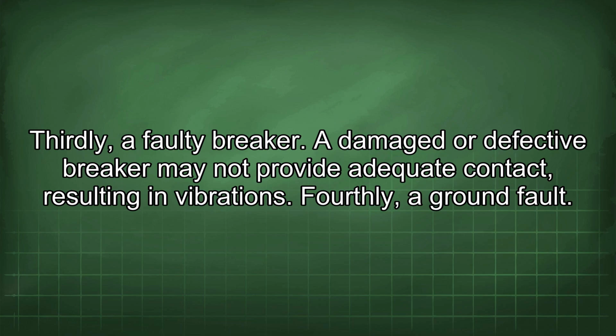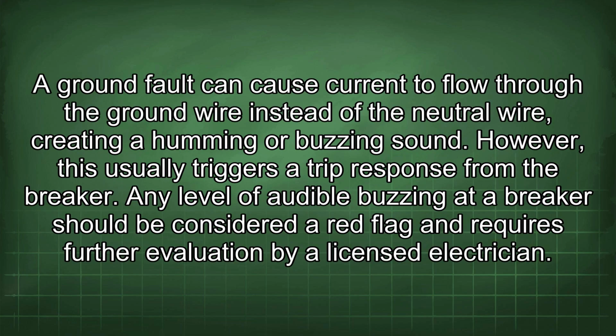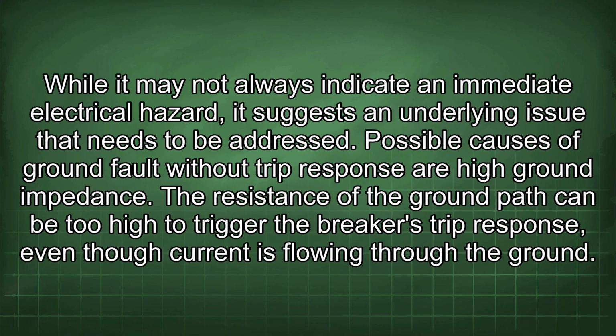Fourthly, a ground fault. A ground fault can cause current to flow through the ground wire instead of the neutral wire, creating a humming or buzzing sound. However, this usually triggers a trip response from the breaker. Any level of audible buzzing at a breaker should be considered a red flag and requires further evaluation by a licensed electrician.